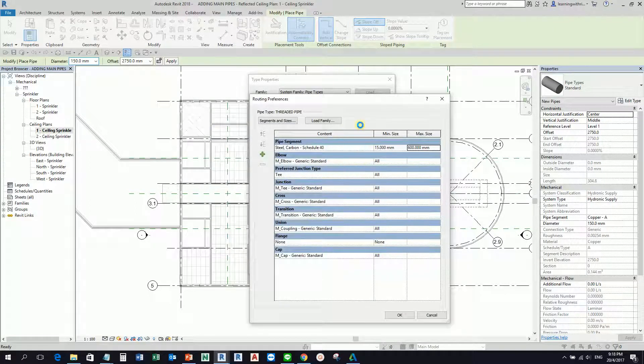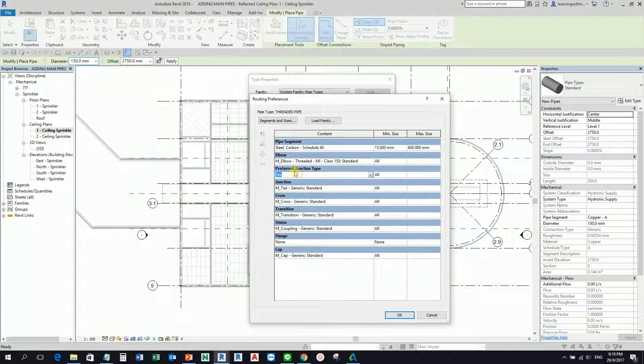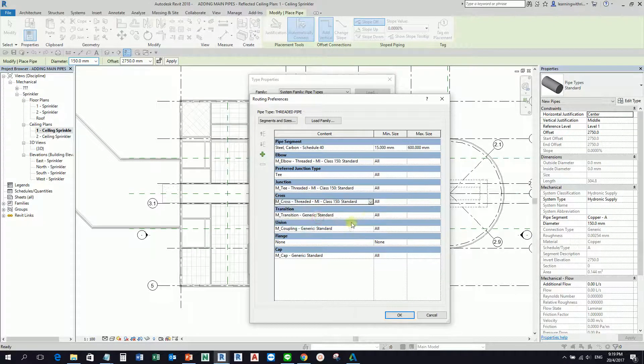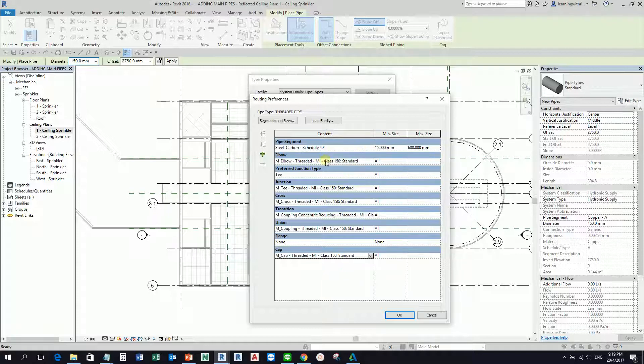The reason I loaded all those families is so I can change the settings of my content. For the elbow, I click the drop-down and select Threaded — or Welded if you prefer. It's already loaded. I'll select Threaded. For the junction type I prefer T, so I select Threaded MI. Cross is Threaded MI, Transition is Threaded MI, Union is Threaded MI — no need for the cap — Threaded MI. That's how you change the content of your pipe type.